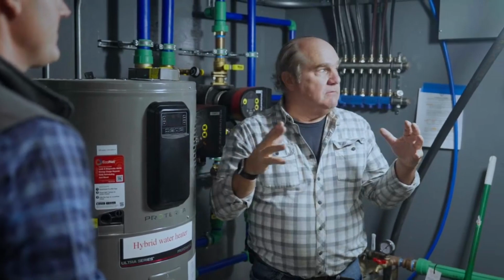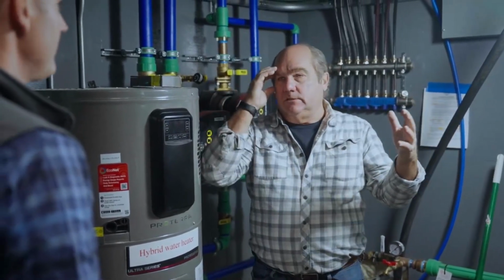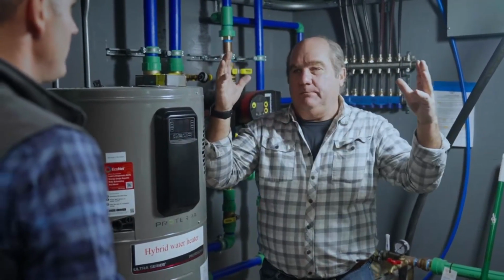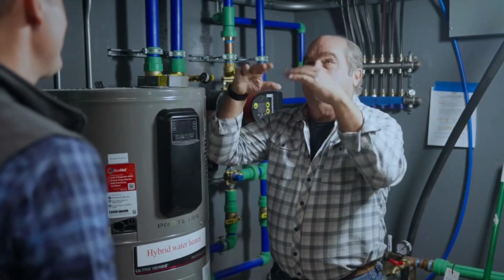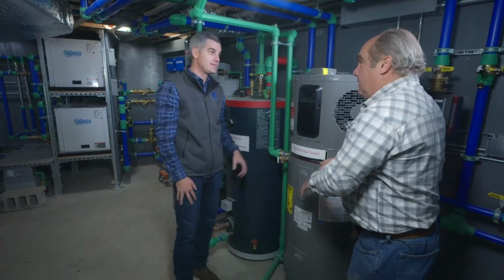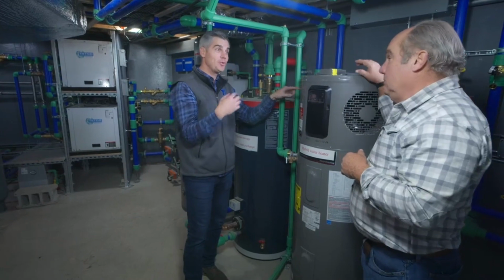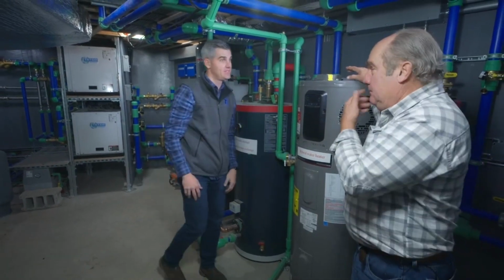And what that does is these rooms can be 90 degrees because you've got all the heat coming off of the pumps and the piping. And so now you'll take that, instead of having it be too hot, have it go right into the hot water, have plenty of hot water. This is going to air condition this room and take that heat and put it into the hot water. Right. It's pretty smart, amazingly efficient.